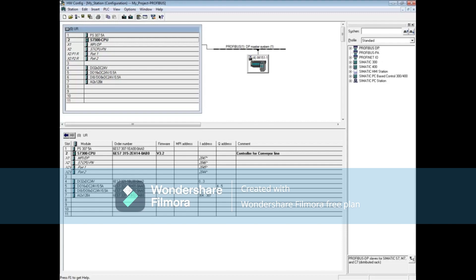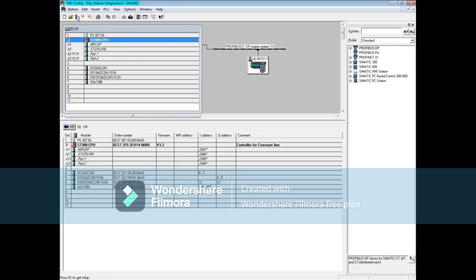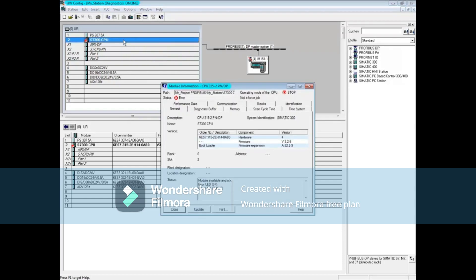In the Hardware Configuration Editor, click the Online button. Placing the Hardware Configuration Online shows a graphical representation of where problems exist. In the Online view, double-click the CPU to open the Module Information Tool. Click on the Diagnostics Buffer tab.